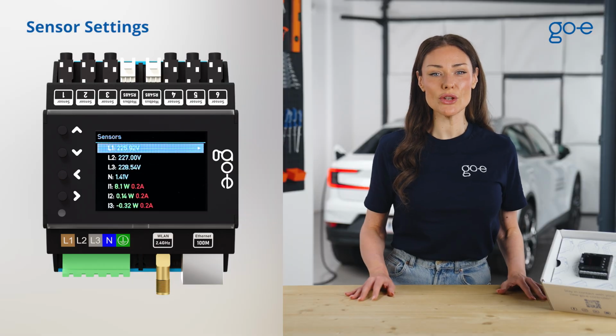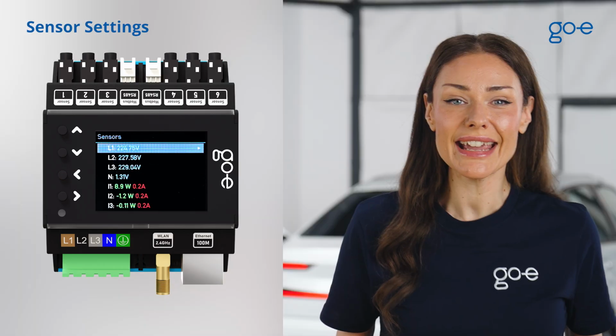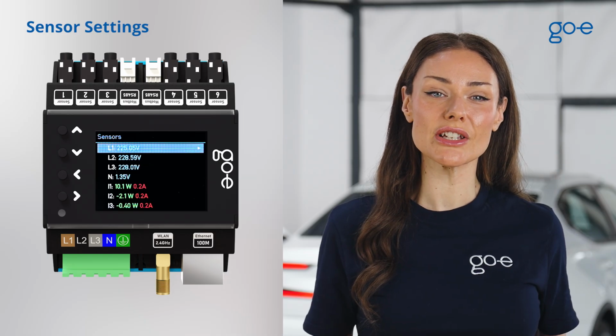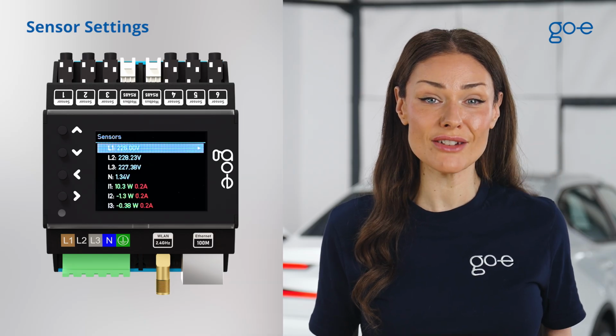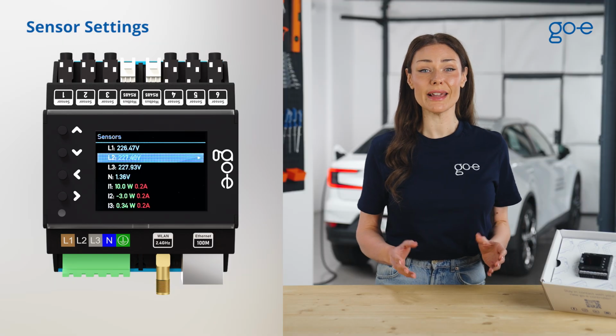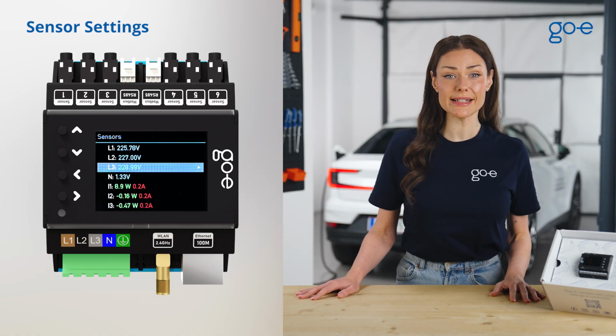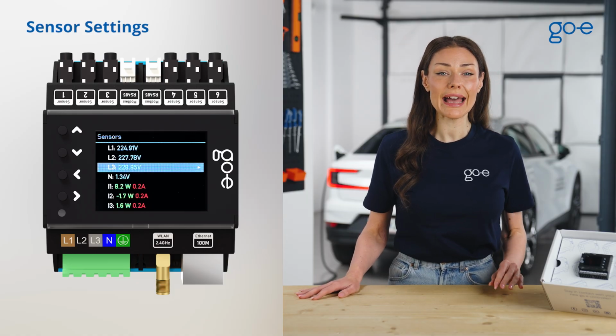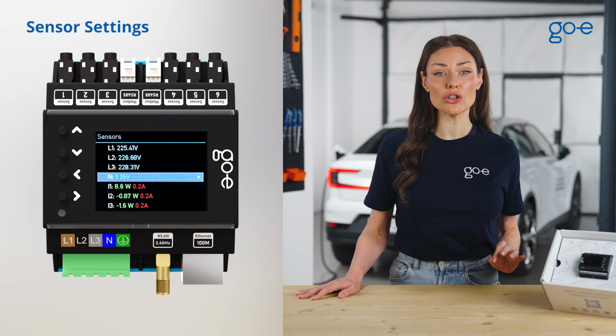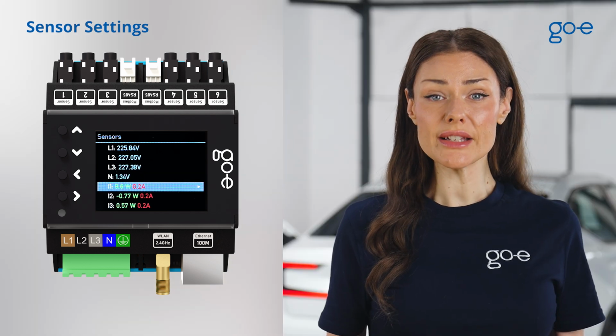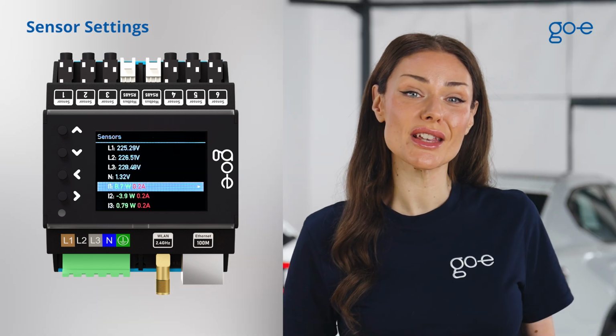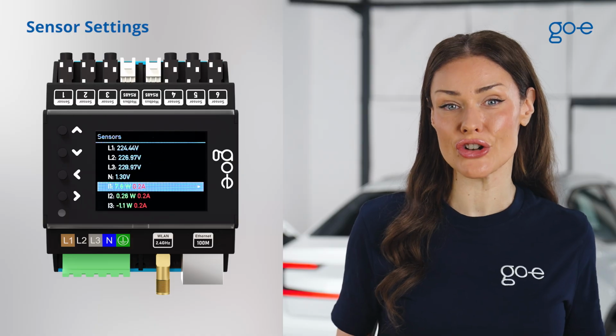In the Sensors menu, you can now start the configuration. In this menu, you can already see voltages, currents, and power values in real time. L1 to L3 show the voltage of the phases connected to the terminal block, and N indicates the connected neutral conductor. I1 to I6 display the values of the connected sensors or current transformers.